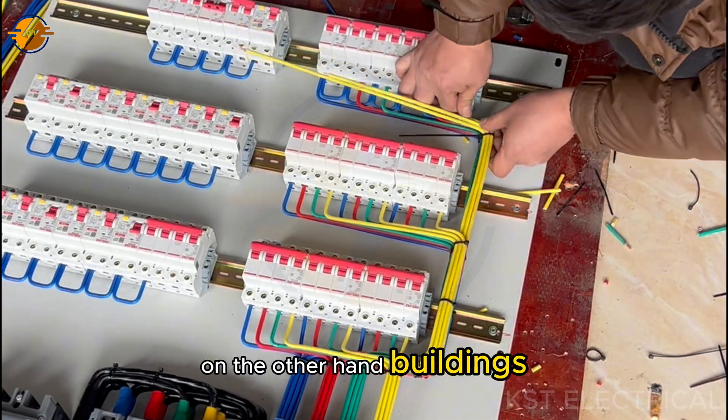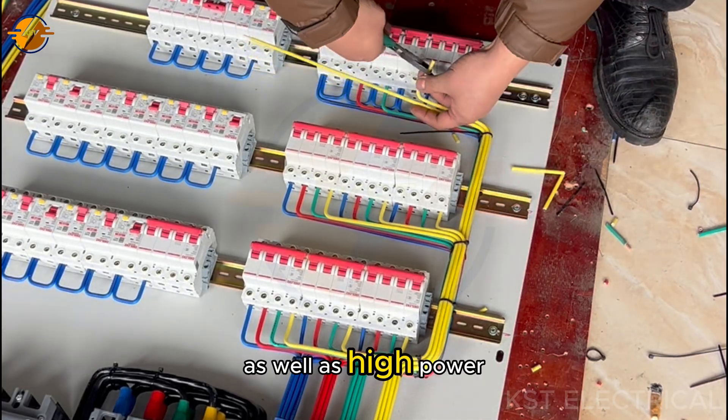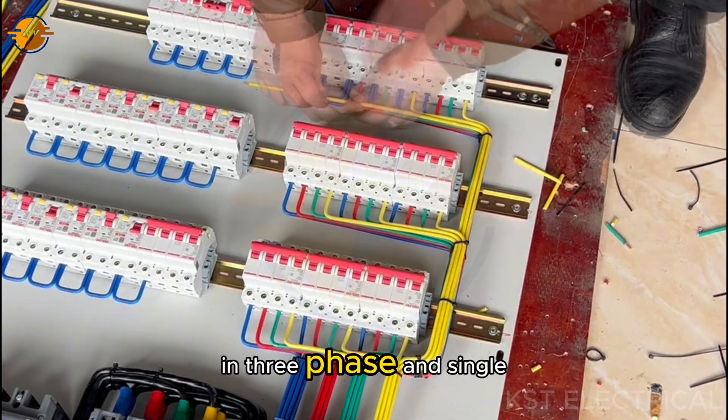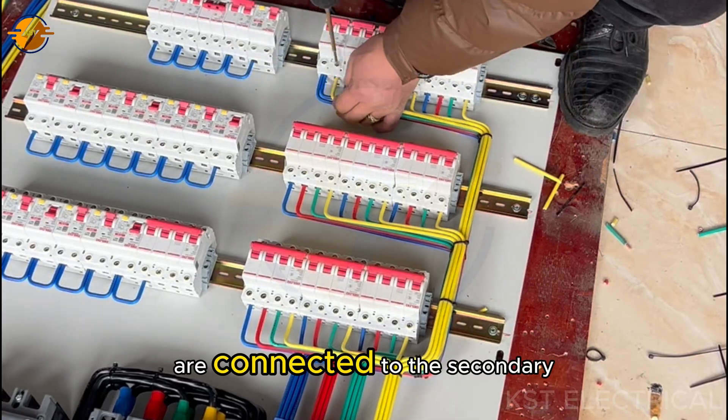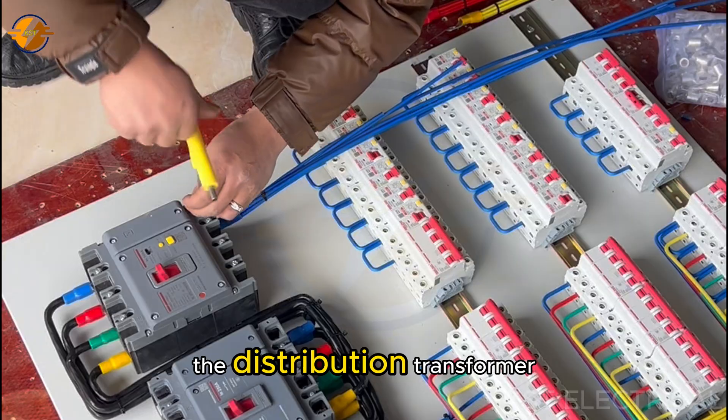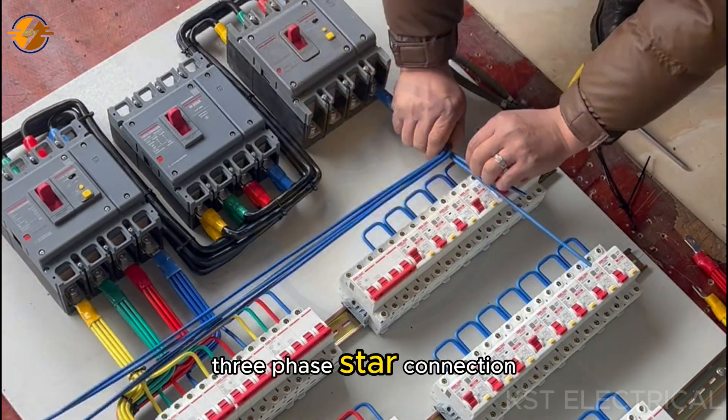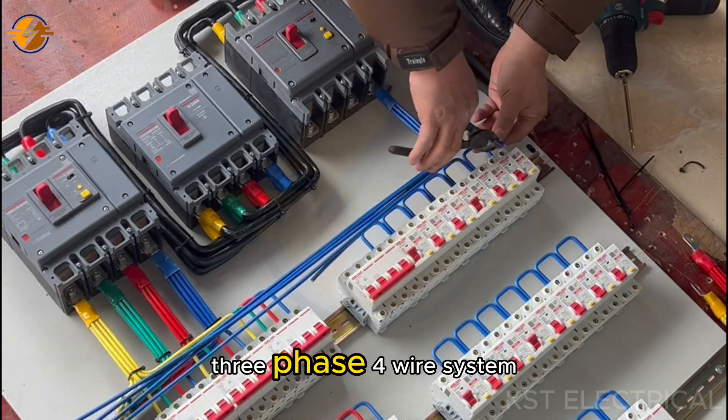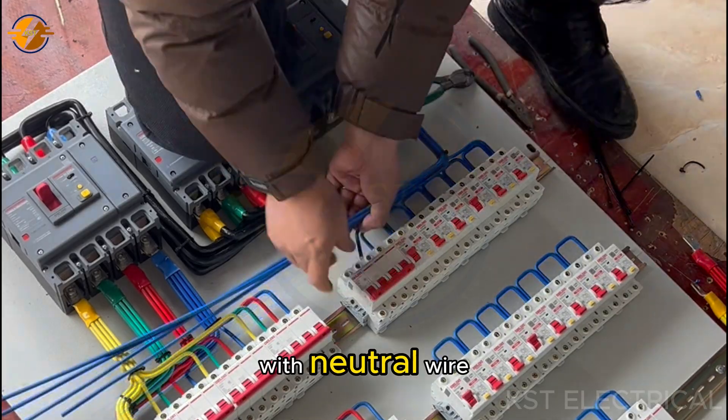On the other hand, buildings that need low as well as high power in three-phase and single-phase are connected to the secondary of the distribution transformer. This way, they get a three-phase star connection three-phase four-wire system with neutral wire.